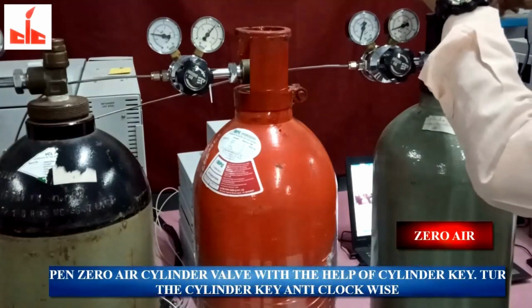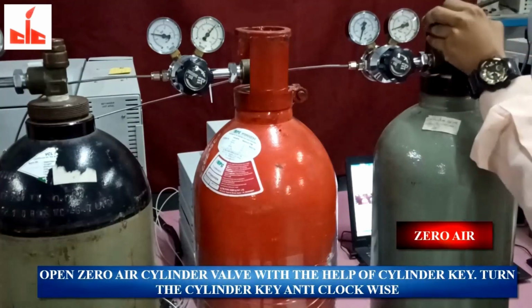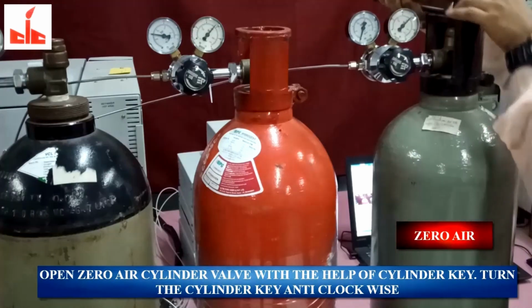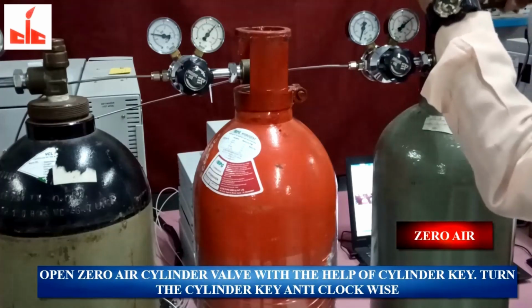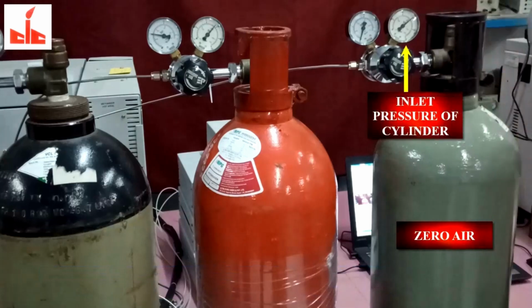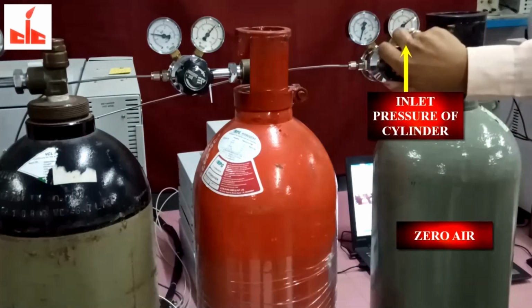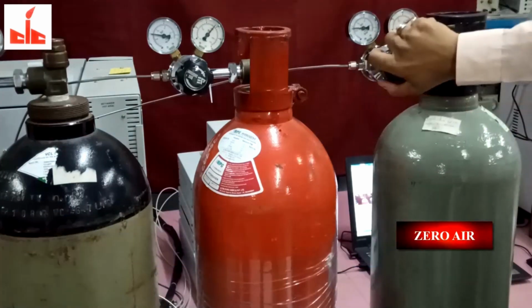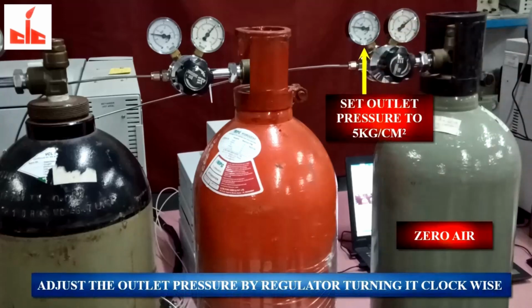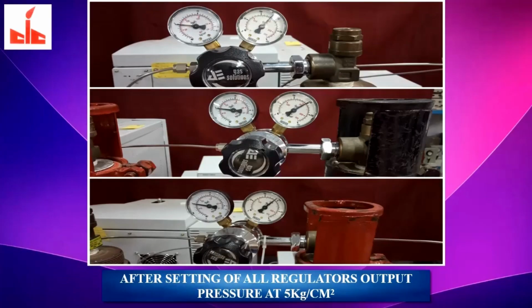Open zero air cylinder valve, with the help of cylinder key. Turn the cylinder key anti-clockwise to open it. Right side pressure gauge shows the inlet pressure of cylinder. Adjust the outlet pressure by regulator, turning it clockwise and set it to 5 kg per centimeter square. After setting of all regulators, output pressure is at 5 kg per centimeter square.